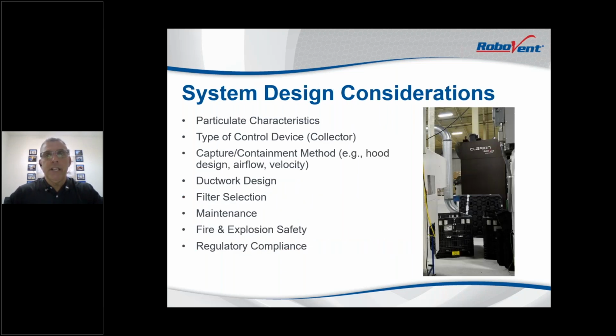System design considerations. When we design the actual mist control system, we talked briefly about particle characteristics: what's in that chemistry, what's in the metalworking fluid, emulsifiers, anti-rust or corrosion properties or chemicals. All those things will have some bearing on the filter selection. What type of control device? Is it a dry collector or wet collector, depending upon what types of particulates we're going to be capturing?